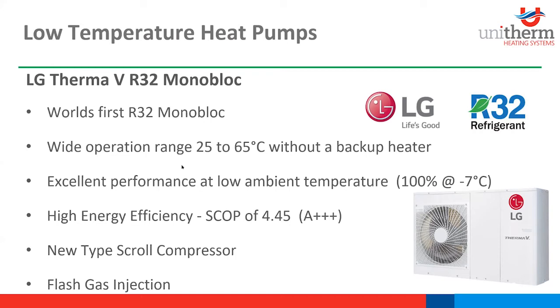So it's the ideal solution for both new builds and also retrofit projects due to its wide operation range. You have a wide operation range there of 25 to 65 degrees without the use of a backup heater. That's fairly unheard of, heating to 65 degrees without the use of a backup heater. Usually you're heating to 50 without a backup heater, and then the backup heater is probably getting you up to 60 to do disinfection once a week or once every 2 weeks. So for NZ buildings, our weather compensated flow is typically between 32 to 38 degrees. That's based on a 75 mil screed.